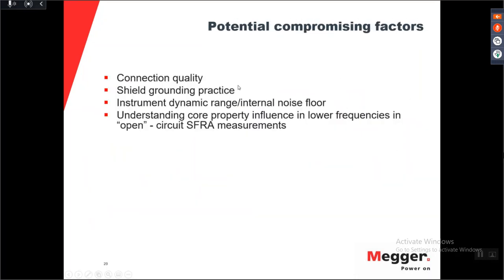When you're doing the SFRA test, there are some things that are very, very important to consider, and something that can actually destroy your test. And it is the connection quality and the shield grounding practice. Then you have the instrument itself, and then how the core properties influence the frequency. This I have already mentioned. You remember how the DC resistance measurement will magnetize the core, and the magnetized core has a residual magnetization, and then your SFRA measurement will be affected by that. So always do the test with a demagnetized transformer. So this can also affect the response.